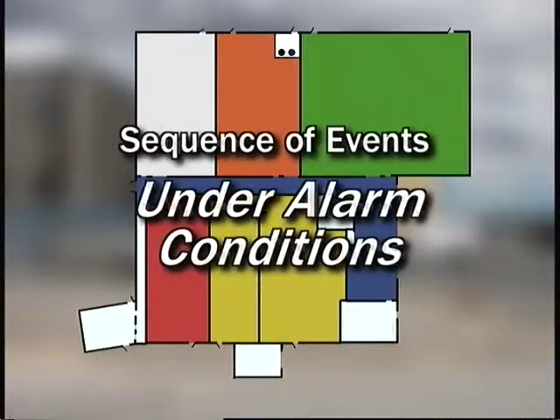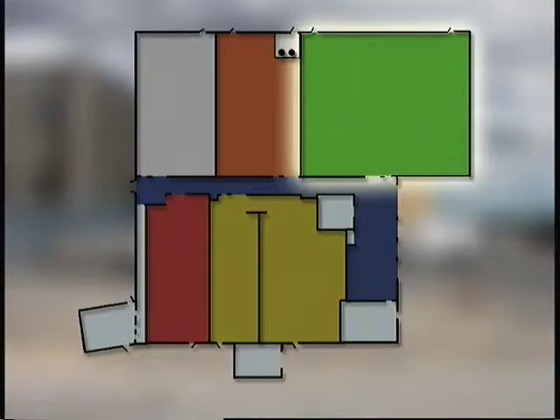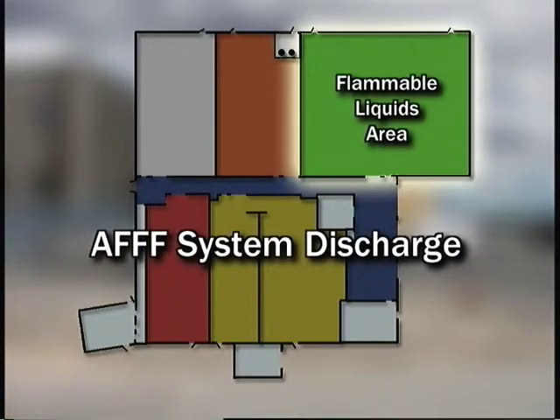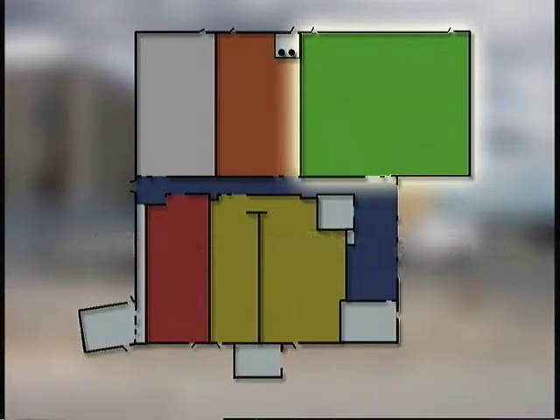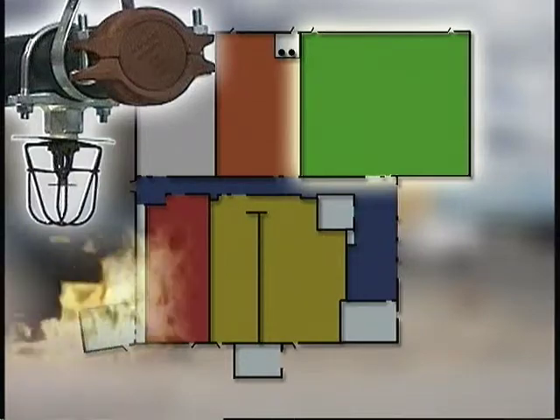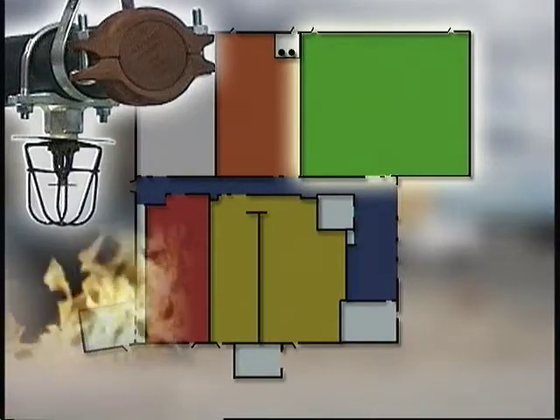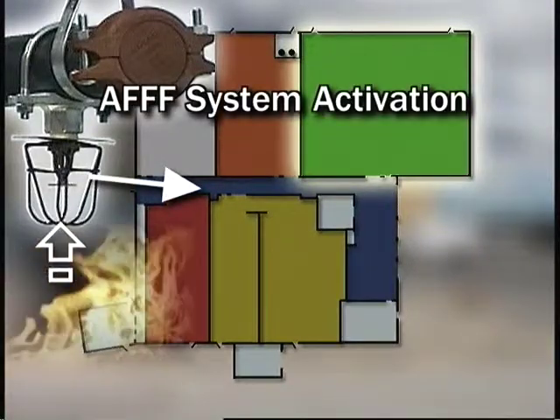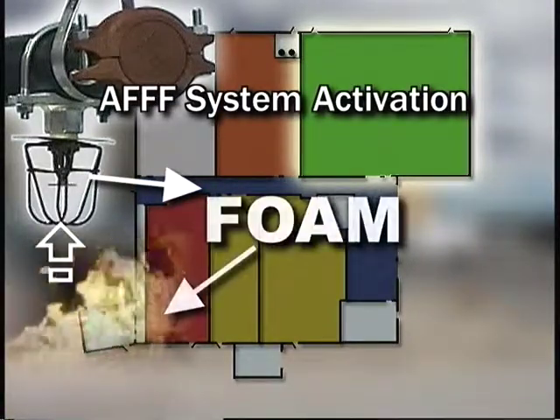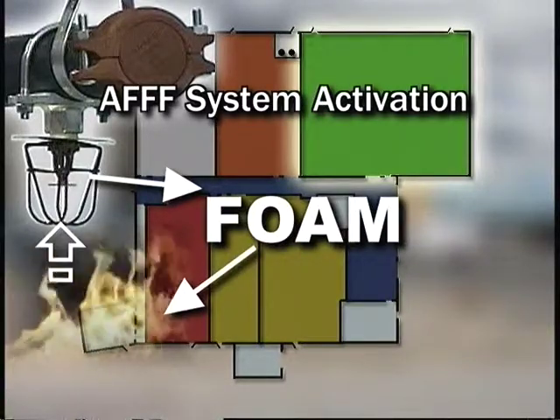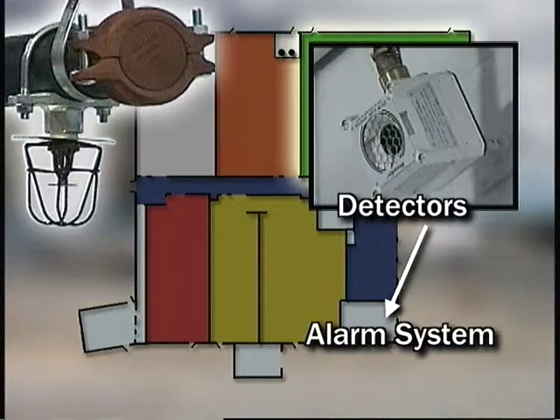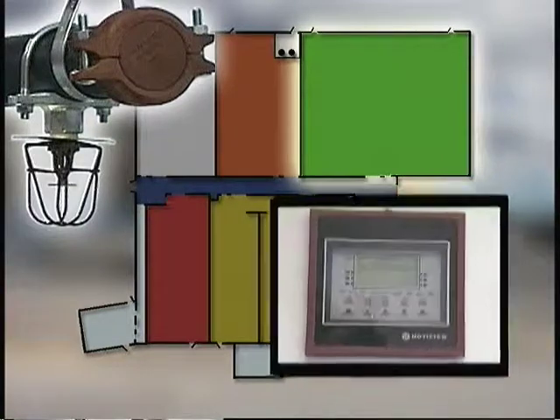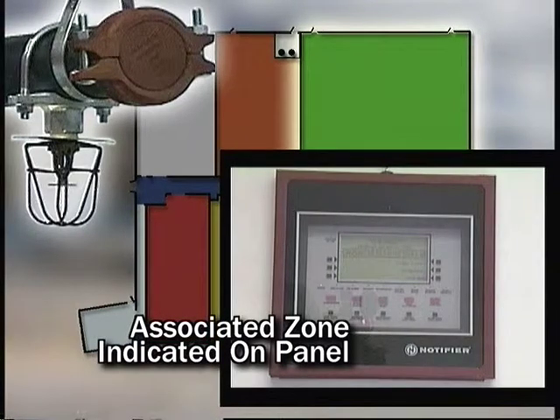The actual sequence of events in an alarm condition depends on where the event takes place. If the alarm condition is in the flammable liquid storage area, it will activate the AFFF system. The likely sequence of events would be as follows. Failure of the heat sensing element will result in immediate system operation in the affected area. The AFFF system will activate, resulting in the discharge of AFFF solution through all of the open heads in the flammable liquids storage room. Heat sensors or flame detectors in the immediate area of the open head will activate the alarm system. The associated zone shall be annunciated on the fire alarm control panel.